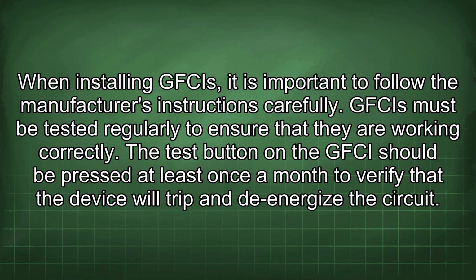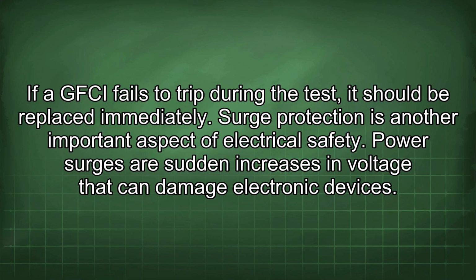GFCIs must be tested regularly to ensure that they are working correctly. The test button on the GFCI should be pressed at least once a month to verify that the device will trip and de-energize the circuit. If a GFCI fails to trip during the test, it should be replaced immediately.